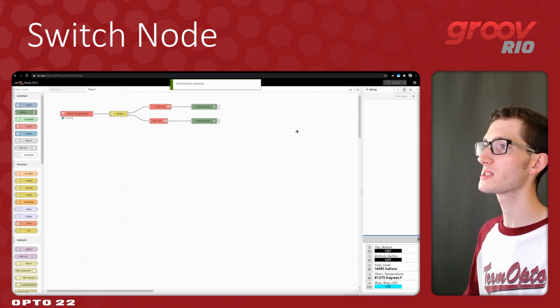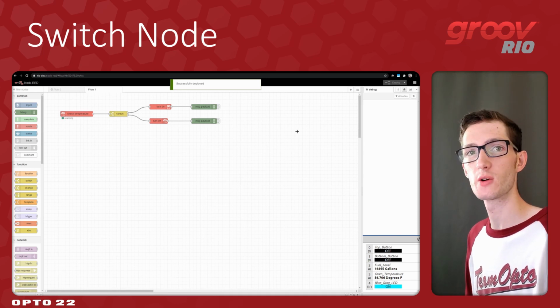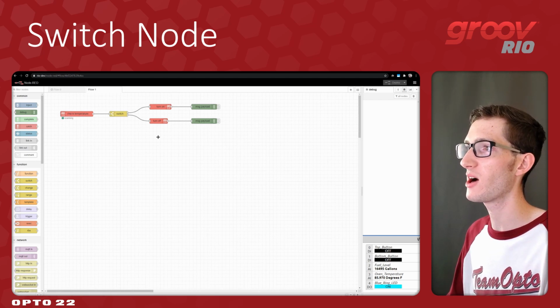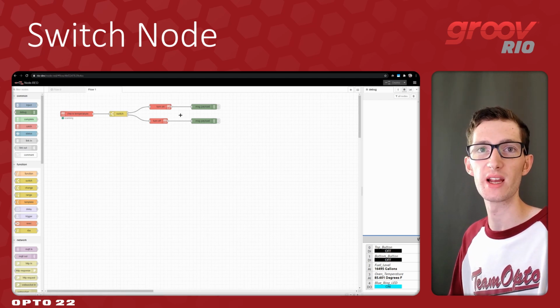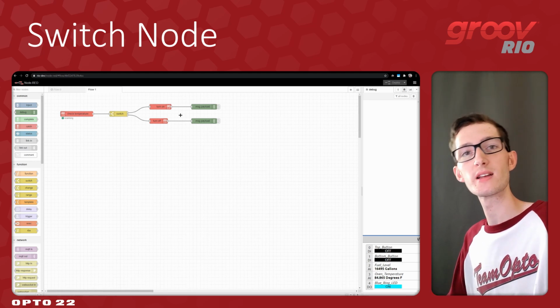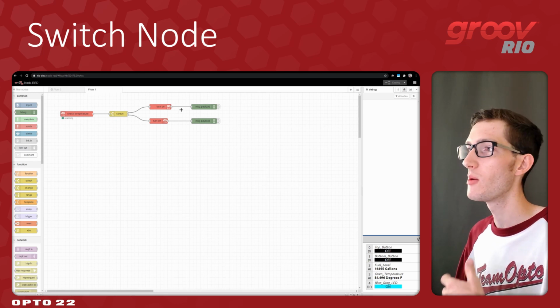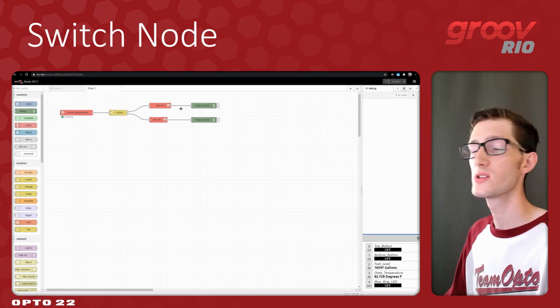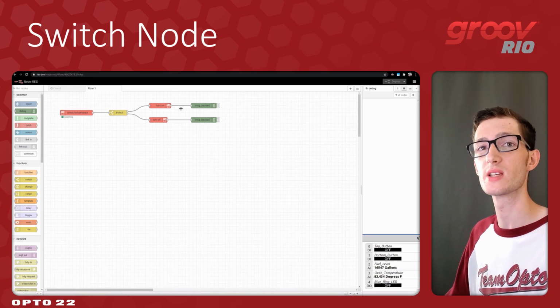So while this works and is really simple, there may be more efficient ways to do this. Because every half degree of change, we are writing this output, and it's simply not necessary. We're saying, oh, you're at 86 degrees, we better turn you on. You're at 87 degrees, we better turn you on. But at that point, it's already being turned on. These are redundant messages. So let's see if we can find a way around this by using another method.